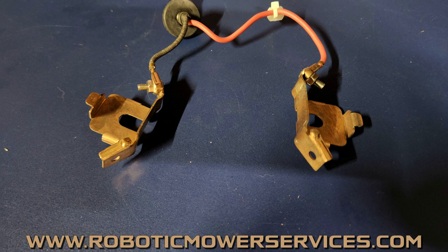The other thing is, you're checking each of these components and you've got to keep track of how much resistance you're finding in each one, because it could be, okay, well I've got 2.5 ohms in this, so that's not too bad. But then I've got 2.5 ohms in this one over here, well that's not too bad. And this one's got 1.5. That all adds up. All that resistance keeps getting stacked on top of each other.